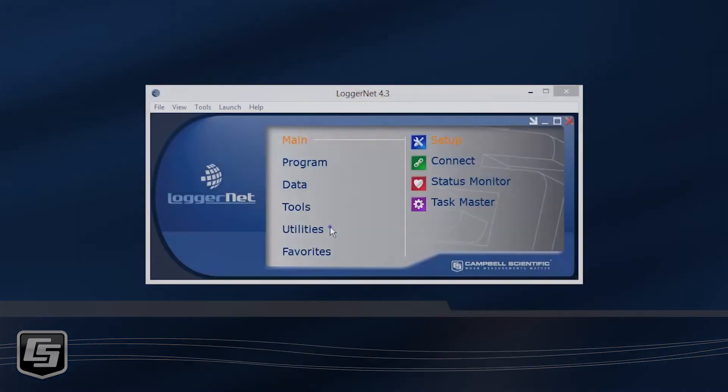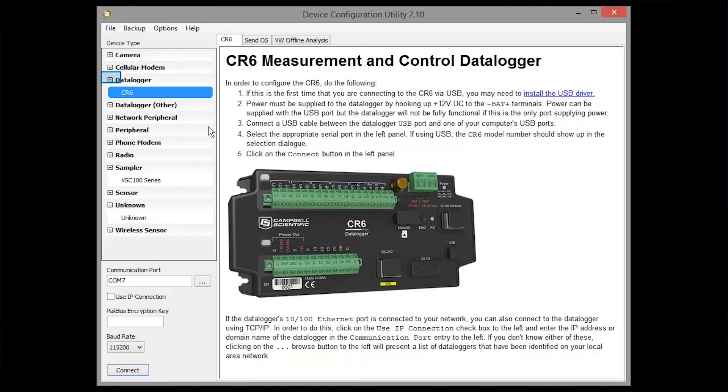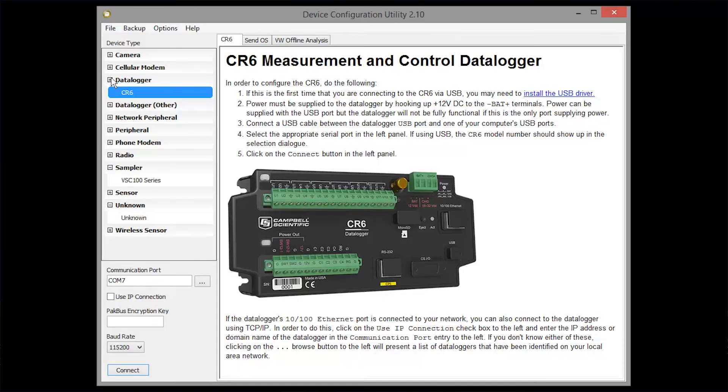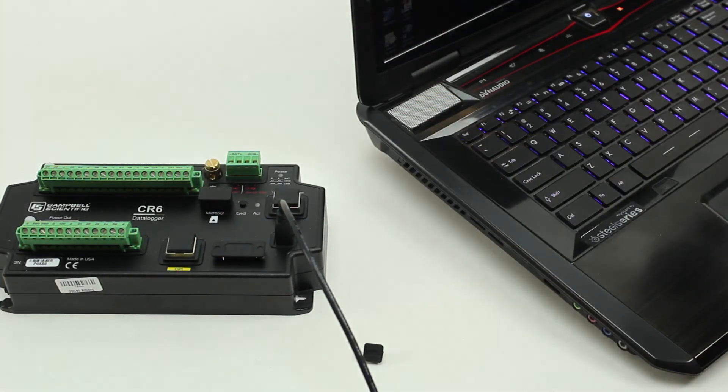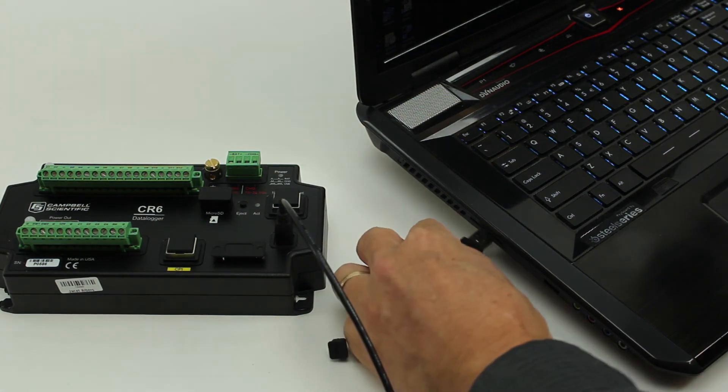For this method, you need to connect your computer to the data logger directly, not over a telecommunications link. The second method I'll show you is sending an OS to a remote data logger — one that's already deployed and could be on a telecommunications link, such as a cell phone or an IP link. Launch the Device Configuration Utility and select your data logger from the list. We're using a CR6. We've already installed the USB drivers, then connected the USB cable from our computer to the data logger.